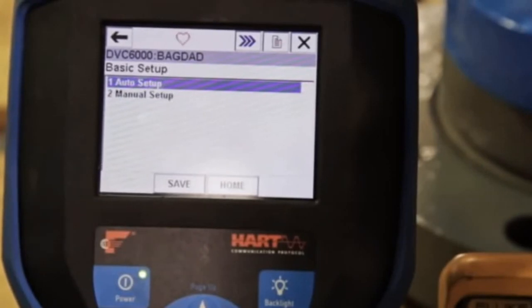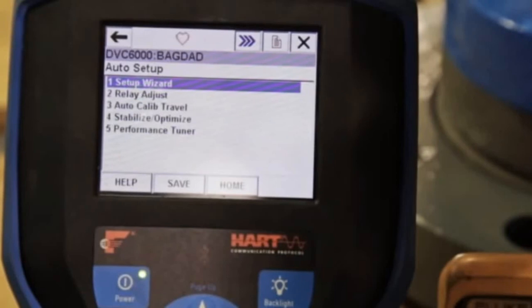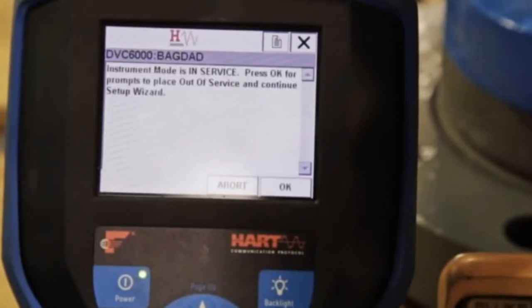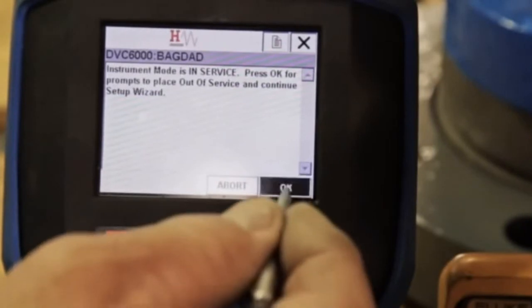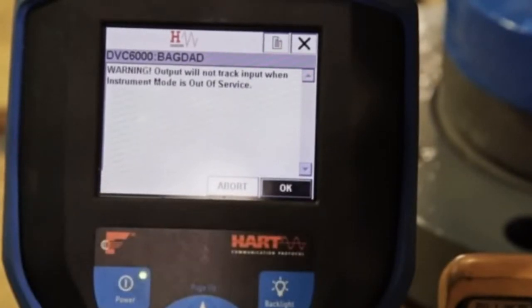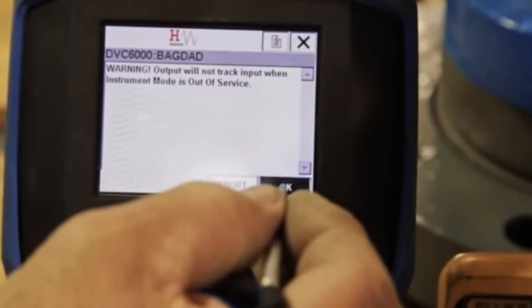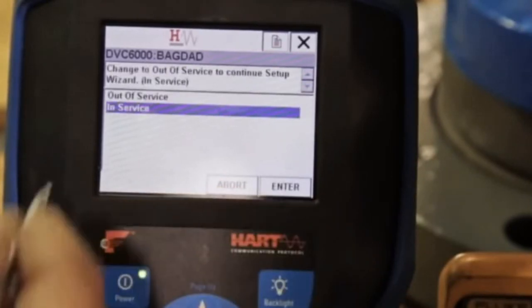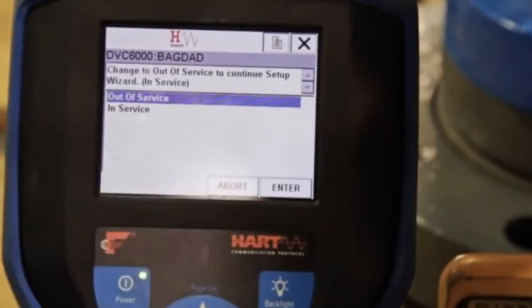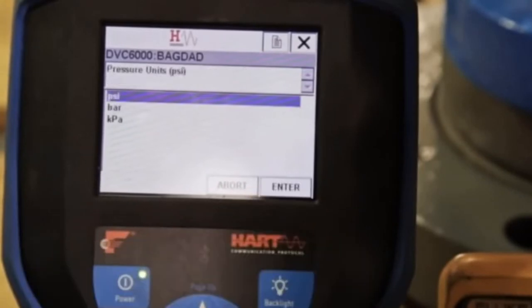Select Auto Setup. Select Setup Wizard. The screen will read Instrument Mode is in service. Select OK for prompts to place out of service and continue. After reading the warning that output will not track input when instrument mode is out of service, select OK. Select Out of Service so the positioner will not follow the inputs from the plant control system.